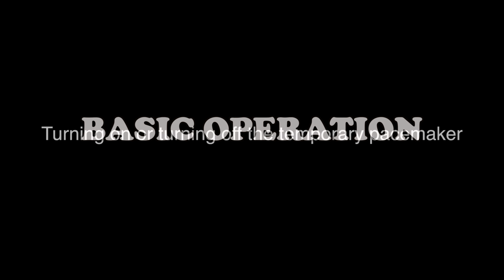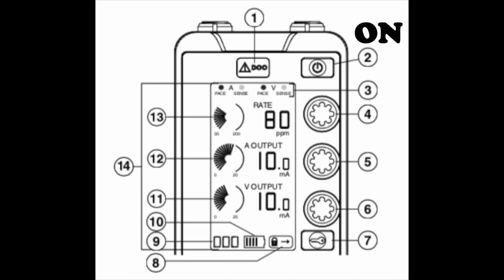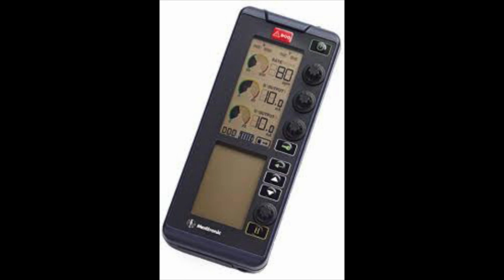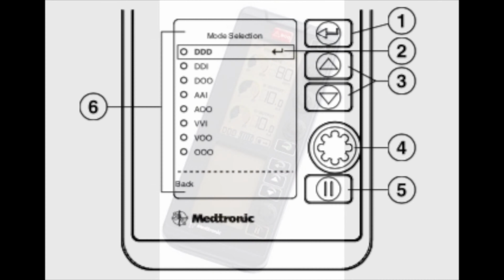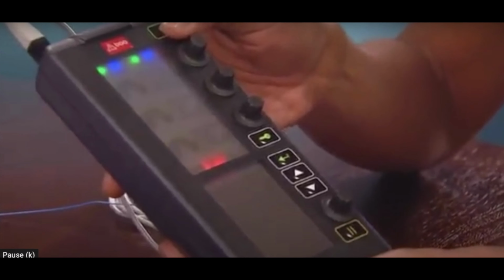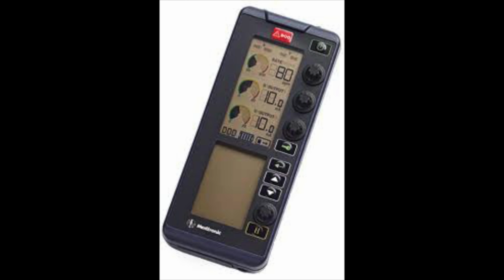Basic operation. Turning on or turning off the temporary pacemaker. To turn on the temporary pacemaker, press and hold the on-off key momentarily. When the temporary pacemaker turns on, the following occurs: a self-test is initiated. When the self-test completes successfully, the temporary pacemaker first searches for cardiac activity during the first pacing cycle, and then begins sensing and pacing in both chambers, DDD pacing mode. The upper screen and the backlight illuminate.